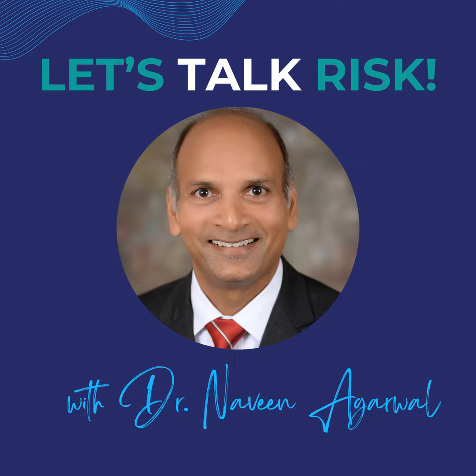So what I kind of talked about before, really linking the reliability from a design perspective and into the risk perspective as well. So you really need a tool to manage it, because it can get complicated pretty quickly. And especially when you're dealing with a somewhat complex device, you need to really have a good way to manage it and track all that. So there are a lot of tools out there that can do that. Generally, most of them fall under the ALM realm or application lifecycle management, which is kind of really an offshoot from the software development folks.